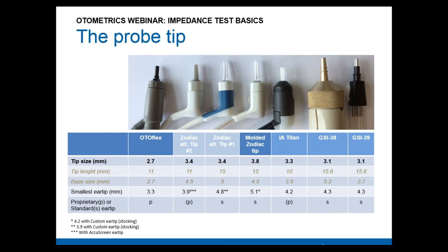Here is an overview of different probe tips we have tested and developed. You can see there is quite a lot of variation. The probe tip diameter should ideally be between 2.7 mm — as seen on the OTOflex — up to about 3.4 to 3.8 millimeters, to ensure you can fit the right ear tip mushroom size.